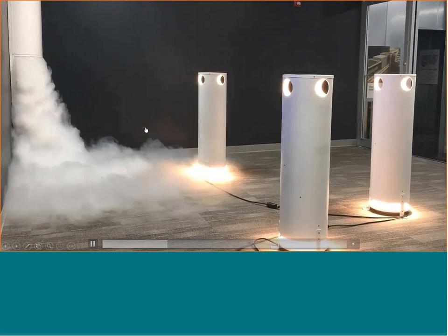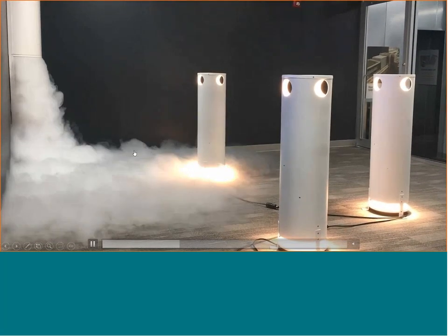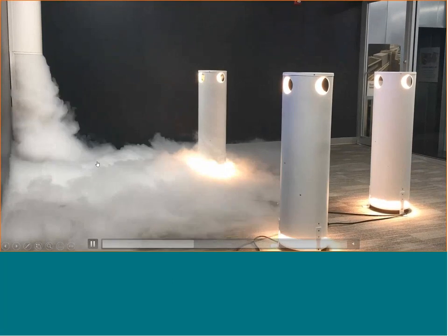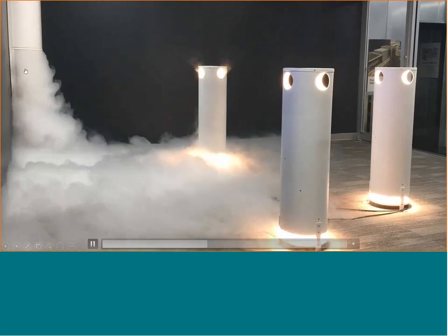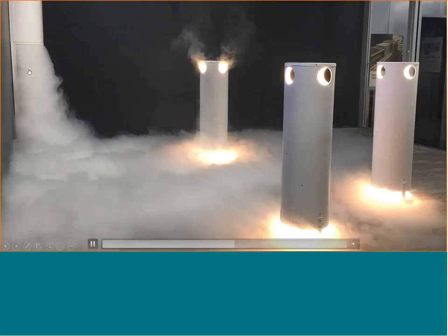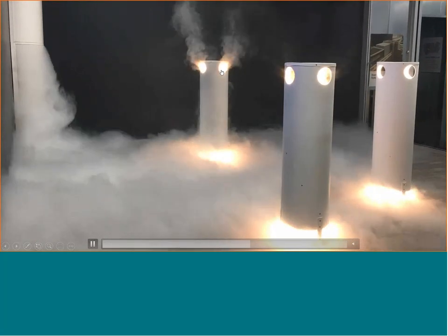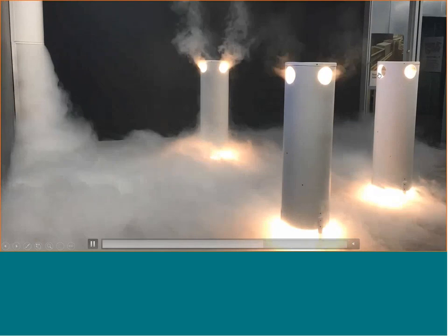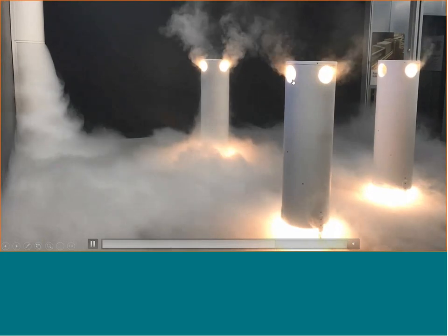So this looks like it's kind of lagging a little bit, but you can see here we're providing a smoke demonstration of about 40 feet per minute nominal face velocity on this diffuser. We're simulating three occupants here with these thermal mannequins.